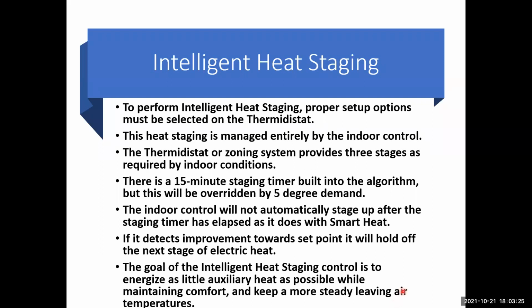The indoor control will not automatically stage up after the staging timer has elapsed, as it did with the Smart Heat. If it detects improvement towards the set point, it will hold off on the next stage of electric heat. The goal of the intelligent heat staging control is to energize as little auxiliary heat as possible while maintaining comfort and keeping a more steady leaving air temperature.